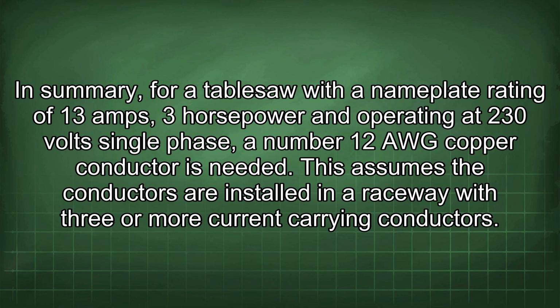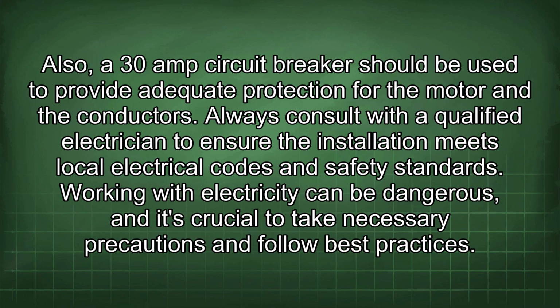In summary, for a table saw with a nameplate rating of 13 amps, 3 horsepower and operating at 230 volts single phase, a number 12 AWG copper conductor is needed. This assumes the conductors are installed in a raceway with 3 or more current carrying conductors. Also, a 30 amp circuit breaker should be used to provide adequate protection for the motor and the conductors.